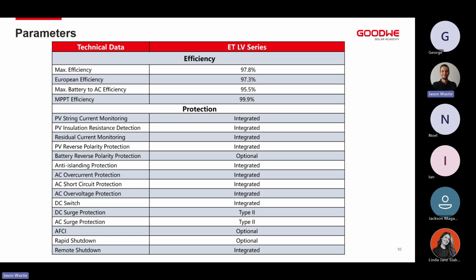Next, we'll look at some of the efficiencies and protections. You'll notice we have PV string current monitoring built in, and insulation resistance detection. So if we've got any bad earthing or shears to your cable or anything, the inverter will be able to pick that up. Reverse polarity protection, as well as all of your AC overcurrent, short circuit current and overvoltage protections, are built into the inverter, within regulation and built to code for the NRS and SANS regulations in South Africa.